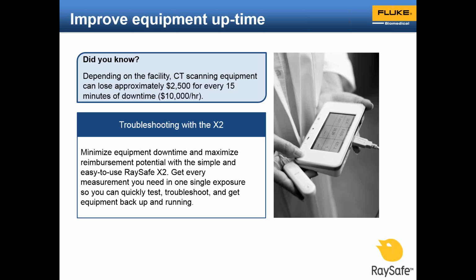Here's an example. Depending on the facility, CT scanning equipment can lose approximately $2,500 for every 15 minutes of downtime, or $10,000 an hour. You can minimize equipment downtime and maximize reimbursement potential with the simple and easy-to-use RaySafe X2. Get every measurement you need in one single exposure so you can quickly test, troubleshoot, and get equipment back up and running.